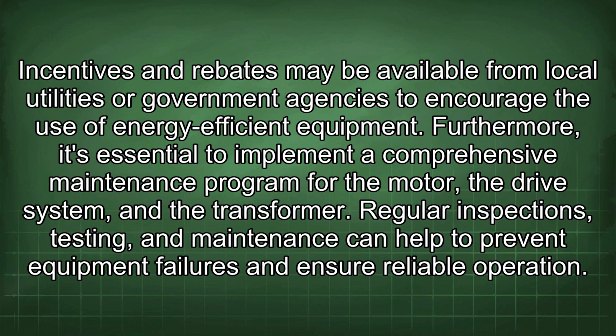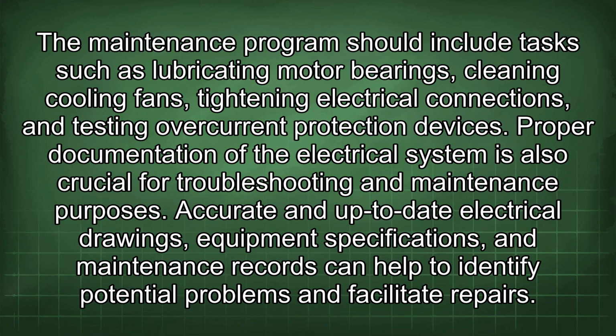Furthermore, it's essential to implement a comprehensive maintenance program for the motor, the drive system, and the transformer. Regular inspections, testing, and maintenance can help to prevent equipment failures and ensure reliable operation. The maintenance program should include tasks such as lubricating motor bearings, cleaning cooling fans, tightening electrical connections, and testing overcurrent protection devices. Proper documentation of the electrical system is also crucial for troubleshooting and maintenance purposes. Accurate and up-to-date electrical drawings, equipment specifications, and maintenance records can help to identify potential problems and facilitate repairs.